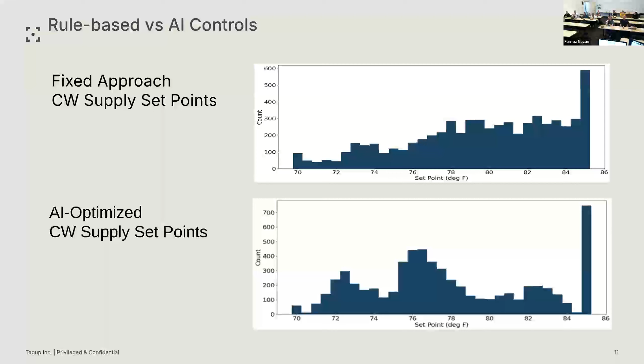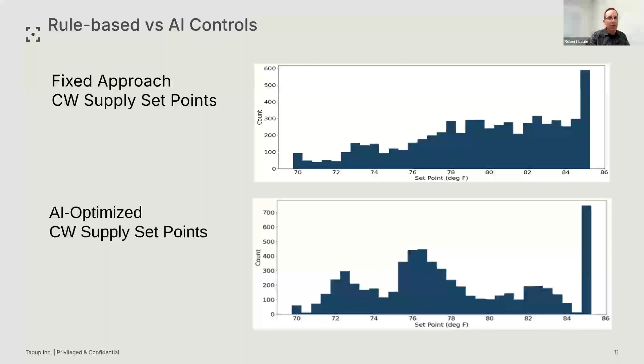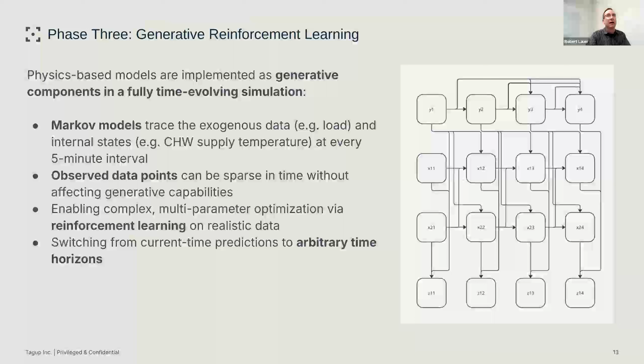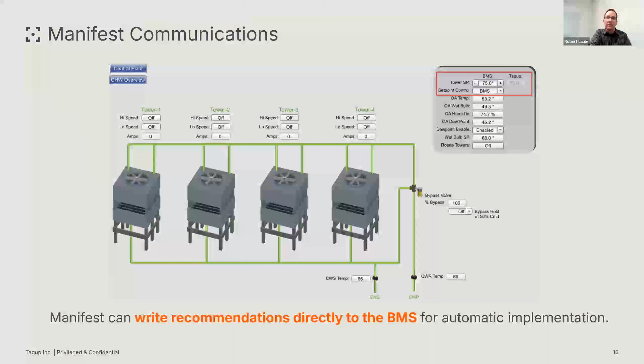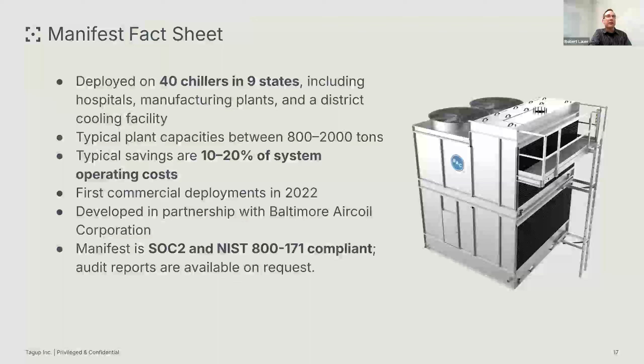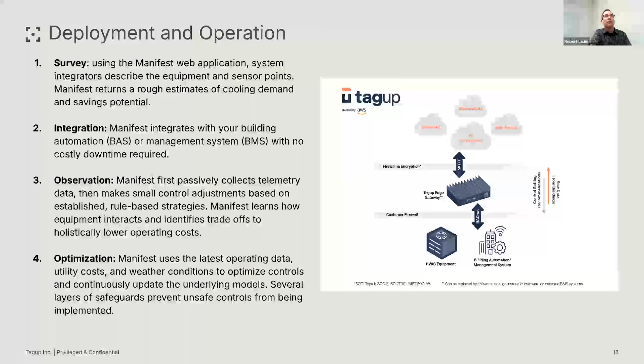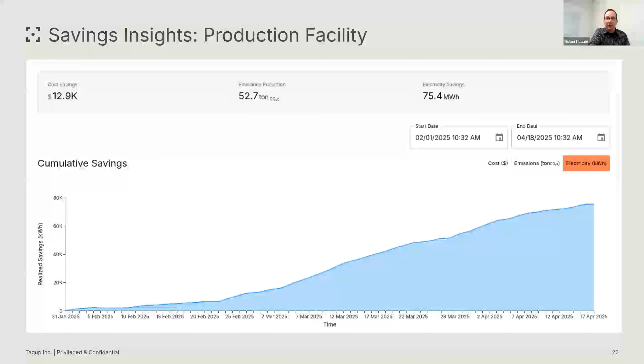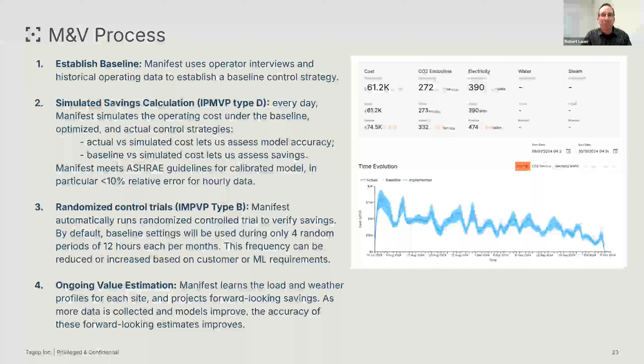For the actual training we use data only from the building itself, but the physics-based setup of the model incorporates expert knowledge about the equipment. The validation is not a traditional on-off type validation. That's part of it, but the actual validation is a type D validation where we bring the simulation to an accuracy level such that even while not running the baseline scenario, we have a precise prediction of what the baseline would have consumed in electricity and water, and then compare and calibrate that prediction on a randomized basis by switching back to the baseline.